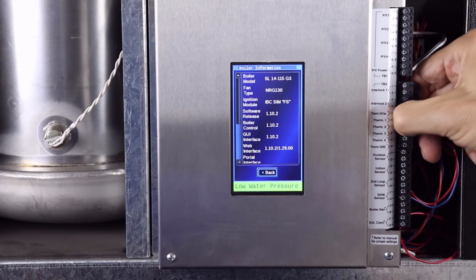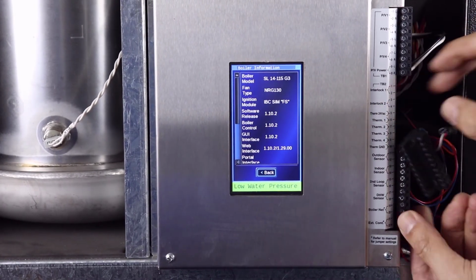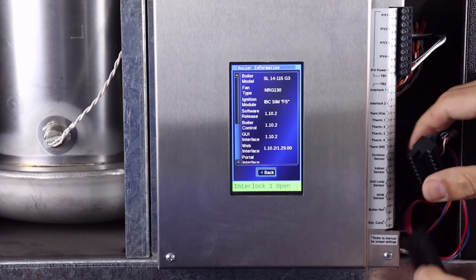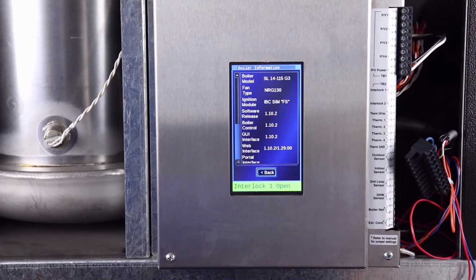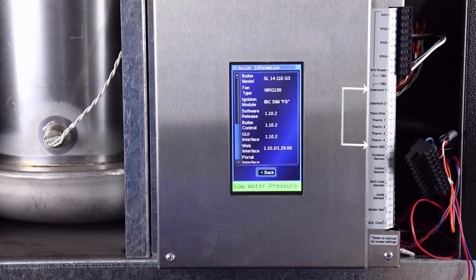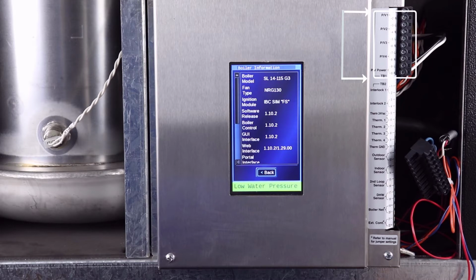These terminal blocks here, these 22 terminals, are the control wires. The upper 10 are the therm connections. You may also have control wiring on the lower 12, for example, a DHW sensor. Pull these terminal blocks straight out and the boiler will not see a call for heat. It's not necessary or recommended to touch the line voltage pump terminals above it.